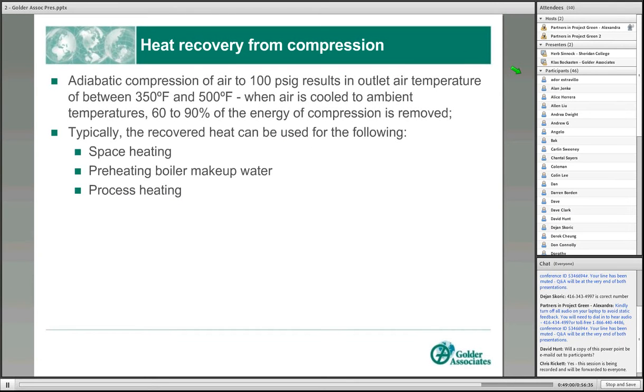Typically under adiabatic compressor conditions, the compressed air output from the compressor would be 350 to 500 F. In a plant where you don't have adiabatic conditions, you would typically see maybe 200 or 250 degree F compressed air temperature. By utilizing heat exchangers and heat recovery, you should be able to generate water in the order of about 120 degrees Fahrenheit to about 150. On oil-cooled systems, the maximum temperature would sit at about 180. So with 120 or 150 degree water, this could be used to provide space heating in the plant.